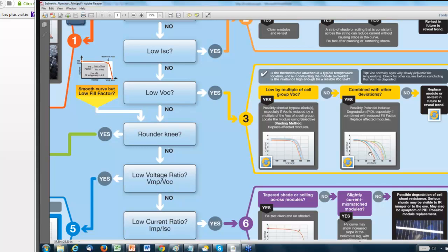It tends to be more prevalent in strings that are biased negative to ground, so it showed up first in Europe, where they have bipolar or floating arrays, with half the string negative relative to ground. It tends to show up on that negative side, and more at the higher, large negative voltages. We're starting to see this in this country too, not only in bipolar or floating arrays, but oddly in negative grounded arrays as well.